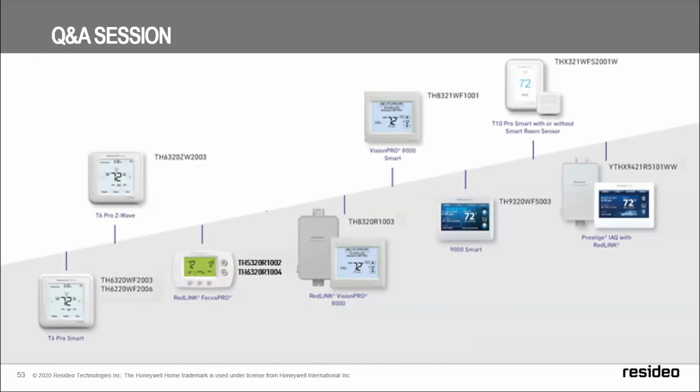If you look there, you see a TH. TH stands for trade home, so that's why you know this is for our channel that we all live in. If it started with an R, it would be retail. And then the 6 or 8 or 9 is the series number. Our Focus Pros are 6, the Vision Pro 8000s are 8, and Prestige is 9. And then there's your heats and your cools. In the case of the 6320, there's 3 heats and 2 cools.